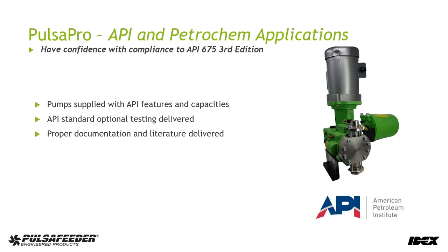Repeatability and linearity, mechanical run tests, sound level tests, positive material identification. We're equipped and ready to provide those services. We already do the standard hydro test and steady state accuracy tests that are required by API as a standard. And as a factory, we have provided for decades pumps in compliance with this that have all the documentation and literature ready to make sure that everything's at your fingertips in order to troubleshoot, evaluate, and make sure that this pump is the right pump for your system.